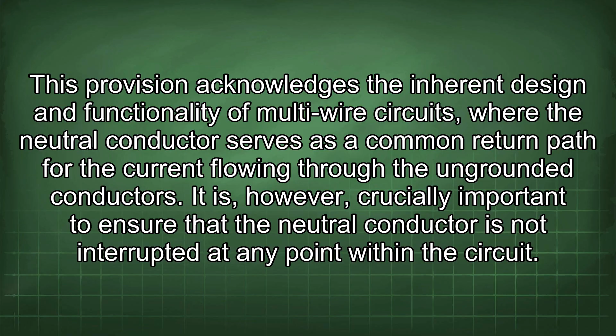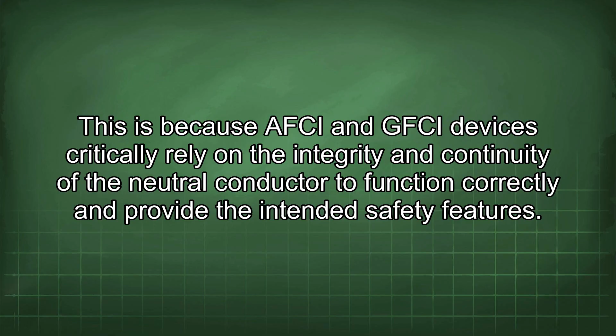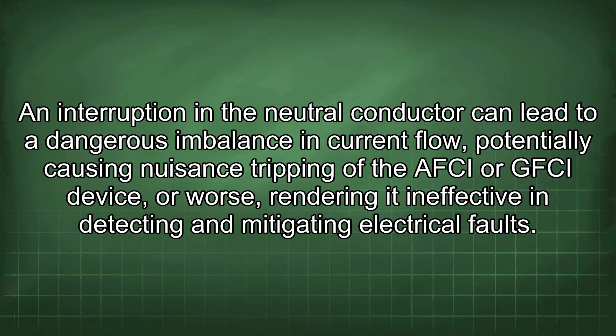It is, however, crucially important to ensure that the neutral conductor is not interrupted at any point within the circuit. This is because AFCI and GFCI devices critically rely on the integrity and continuity of the neutral conductor to function correctly and provide the intended safety features. An interruption in the neutral conductor can lead to a dangerous imbalance in current flow, potentially causing nuisance tripping of the AFCI or GFCI device, or worse, rendering it ineffective in detecting and mitigating electrical faults.